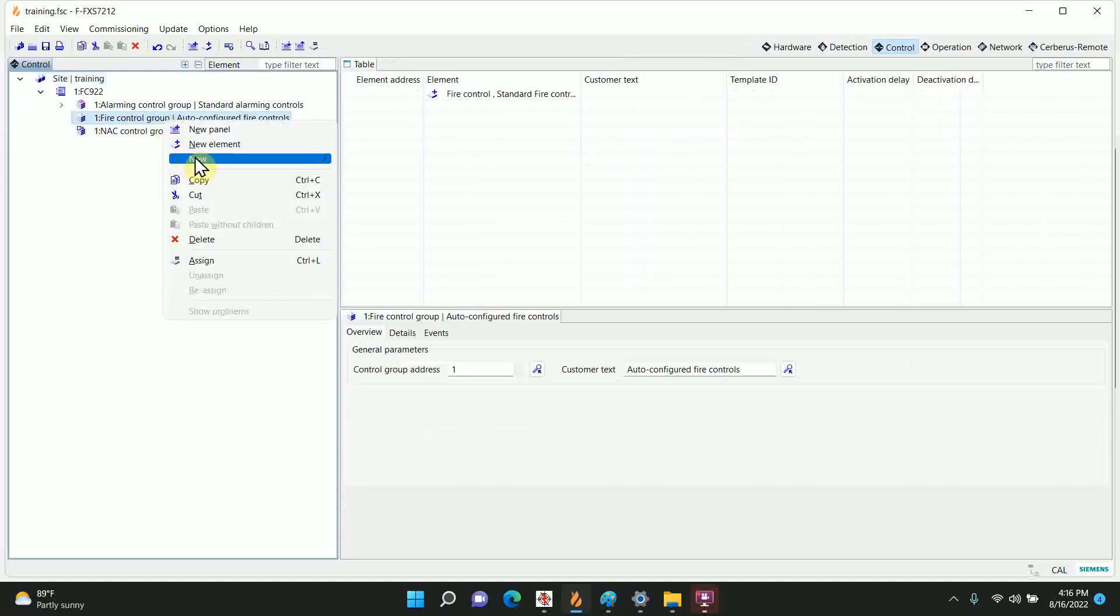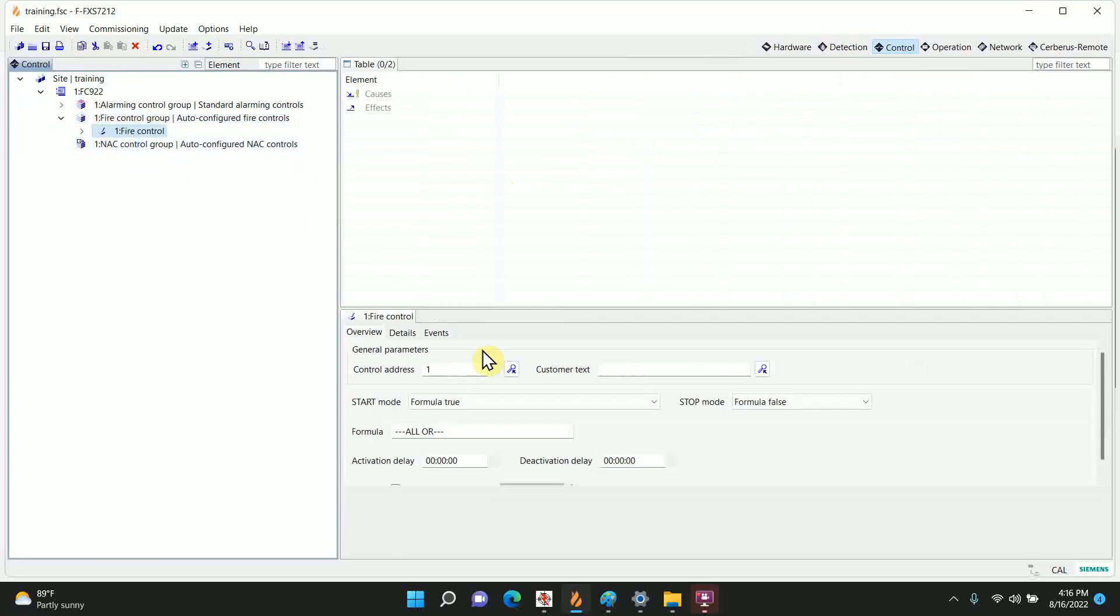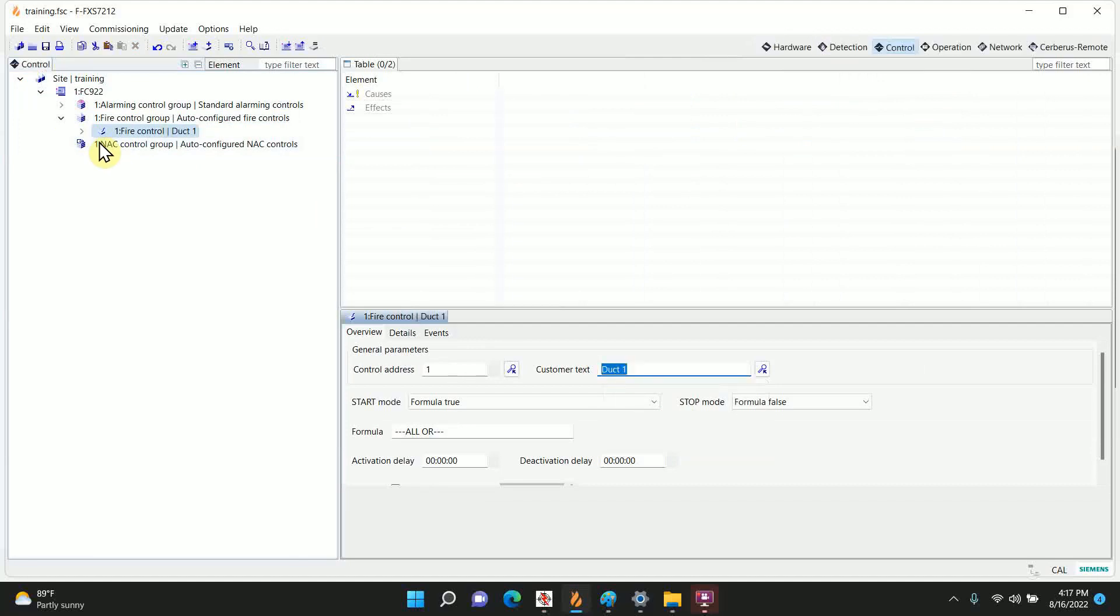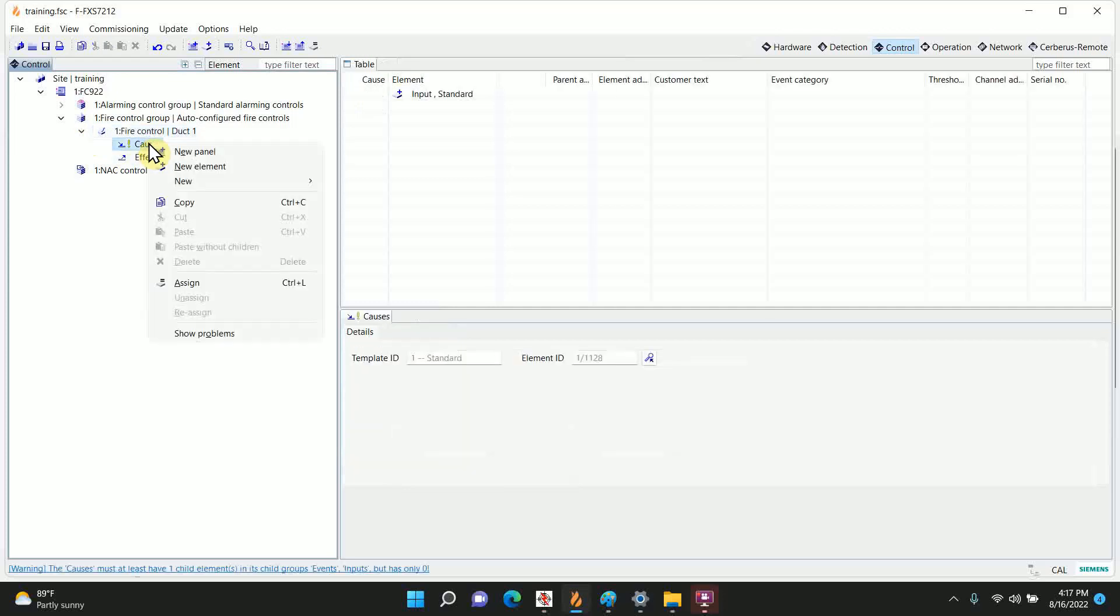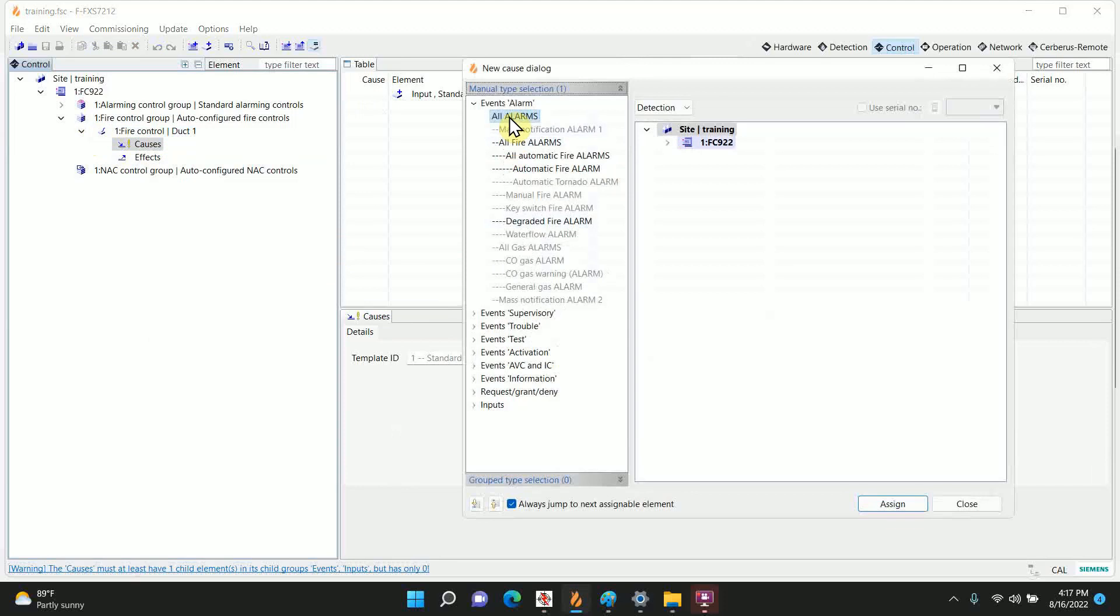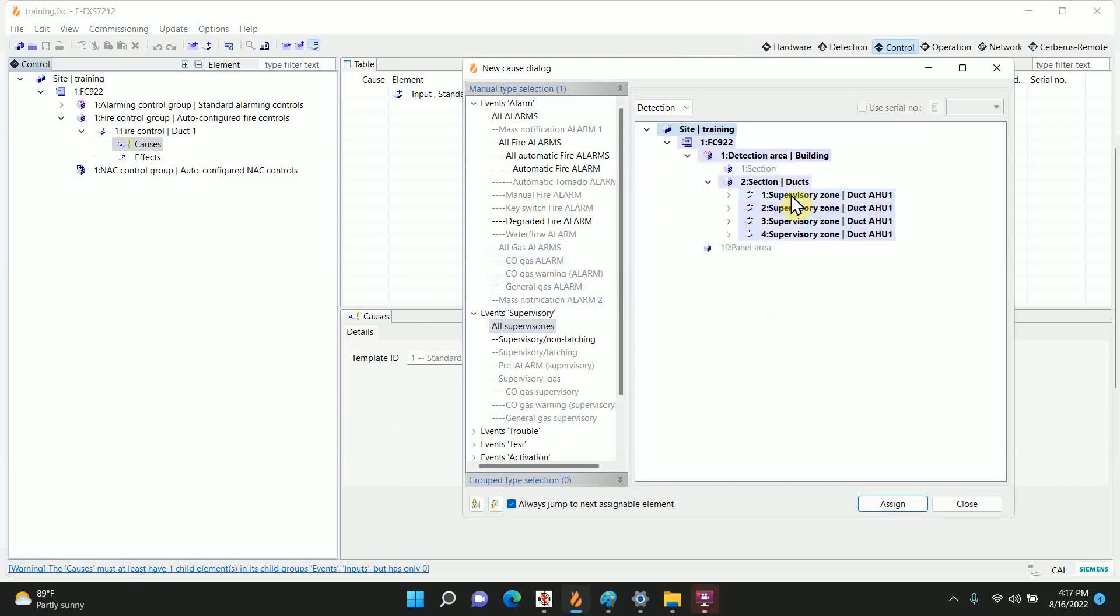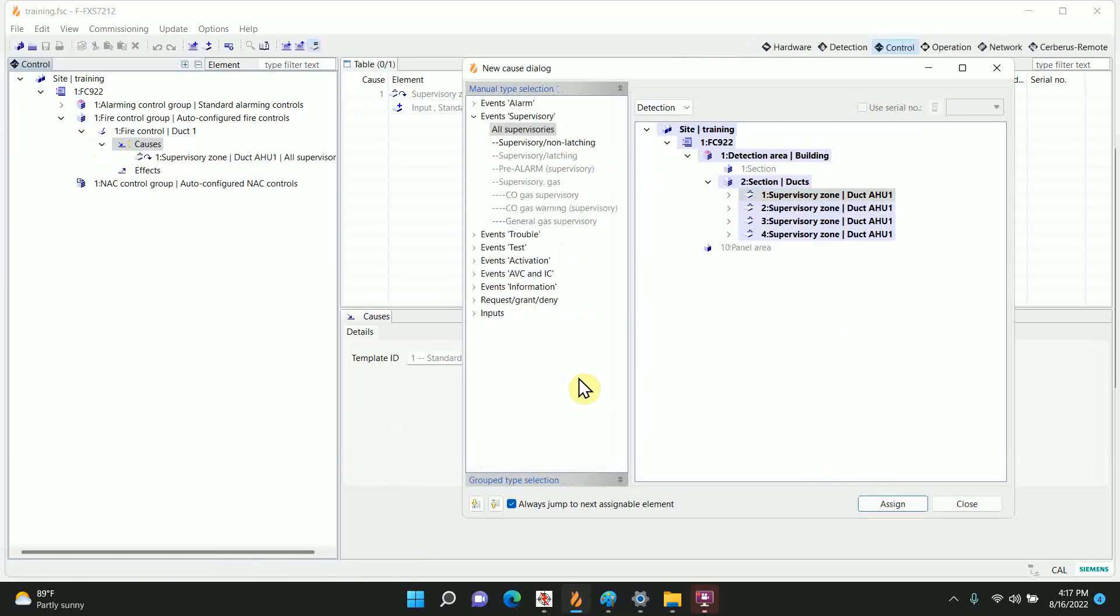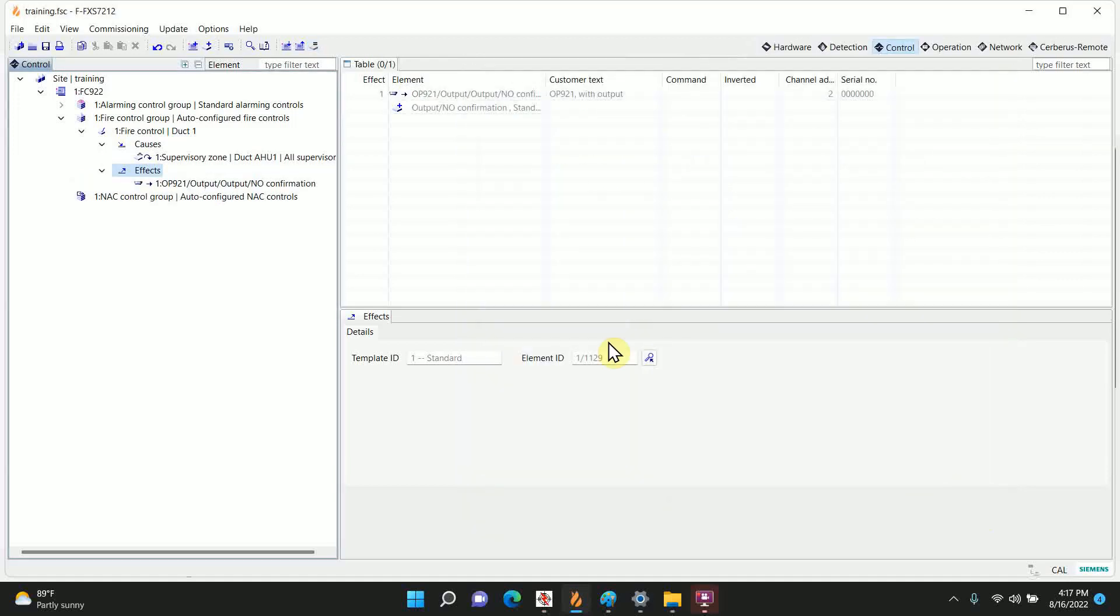In fire control group, I'm going to right-click and hit new fire control, standard fire control. And we'll just call this duct 1. Now if this was just one duct detector or one air handler, you'd just go to cause, assign. And right now it starts us off in alarms but we have supervisors, so we only want to go to event supervisory. Let's open it up, oh there it is right there. Supervisory zone Duct AHU1, we're going to assign that. And I'm not going to close this window, I'm going to go over and click on effects. Output, no confirmation. I want the output associated with the same device and close.